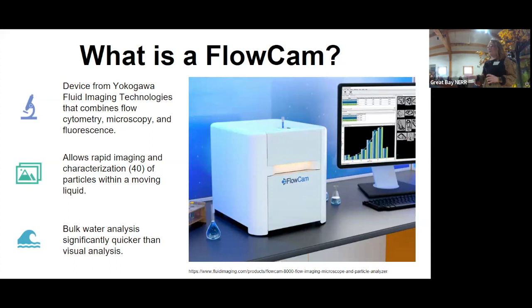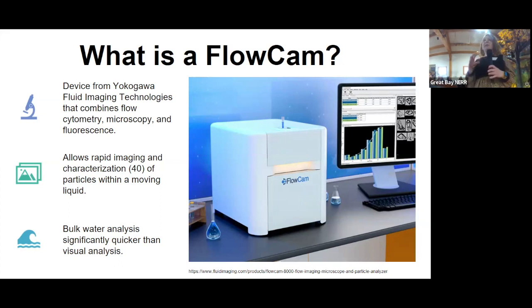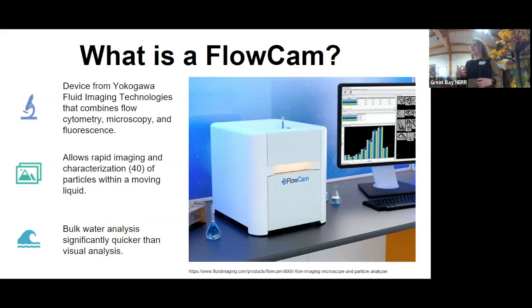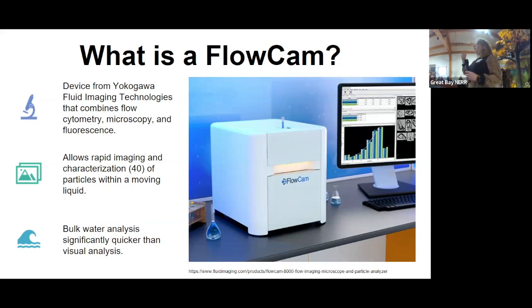I'm just going to talk really quickly about what a FlowCam is. This is a device from Yokogawa Fluid Imaging Technologies, and they essentially combine the ability to do flow cytometry, microscopy, and occasionally fluorescence. That is an option you do have to choose or pay extra for — we don't have that option, but it can be really useful depending on your research. It essentially allows rapid imaging and characterization of particles within a moving liquid. It will suck your liquid down through your pipette, as you see in the middle here, goes to the flow cell, takes images, and looks at everything that's within the liquid.